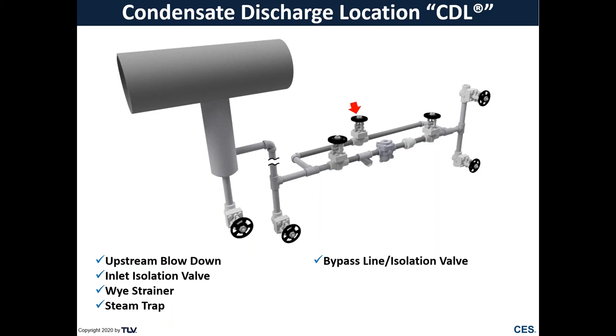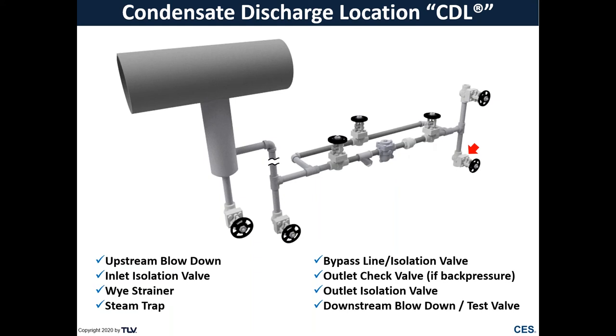Now, for critical applications, we might have a bypass to make sure that we always have condensate drainage in the event that our steam trap becomes blocked or the steam trap requires maintenance. So you may or may not see that bypass valve. We have an outlet check valve if we're returning to a condensate return header that has a back pressure, as well as an outlet isolation valve and a downstream blowdown or test valve, which is going to allow us to see that condensate discharge to atmosphere for steam trap troubleshooting.